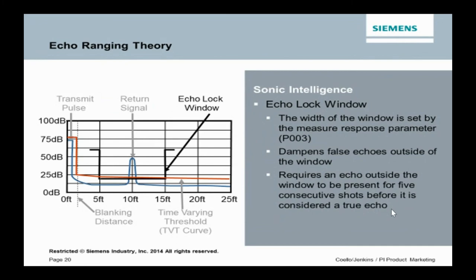If you go and look at our book on parameter P003, it doesn't do a great job of explaining what's going on there. But it is talking about the rate of change. So if you have a process that's changing very, very quickly, you do have to open up that echo lock window, for something that is moving, say, 10 feet per minute in your tank level change. Then you'd have to go to fast. A slow is plus or minus about 4 inches per minute. Medium is about 3 feet per minute. Fast is anything greater than 3 feet per minute. Okay.